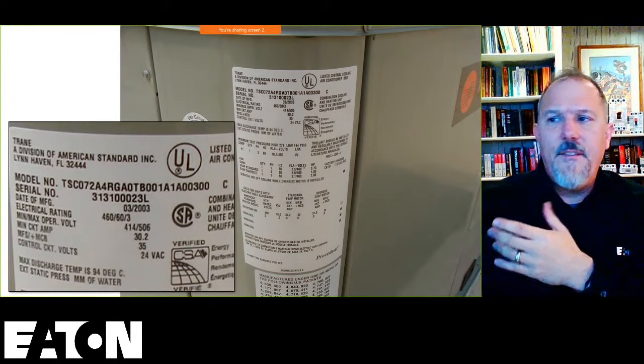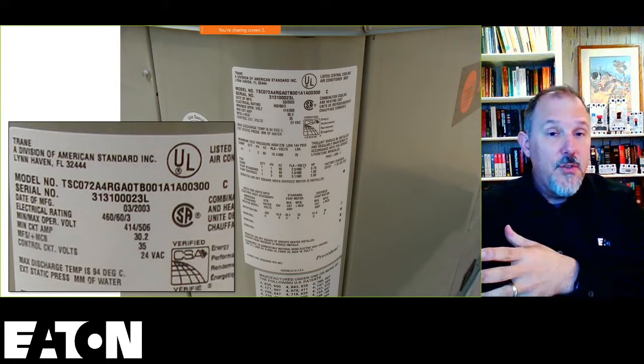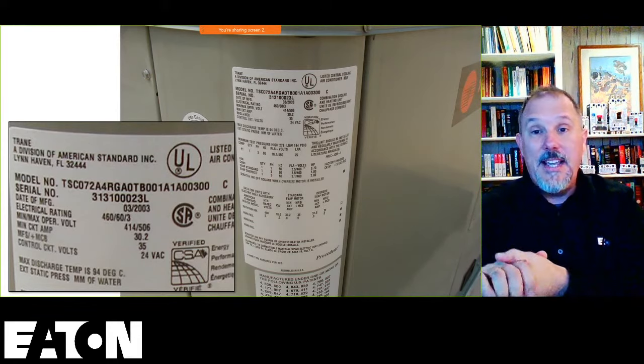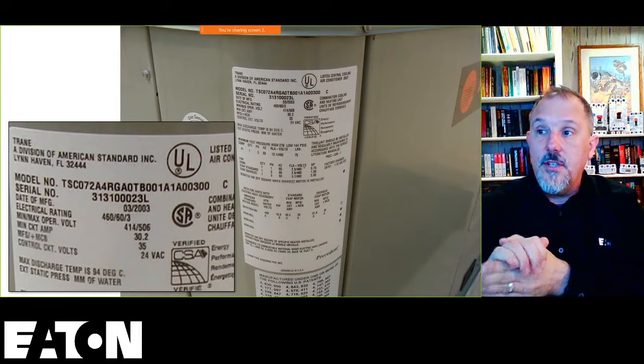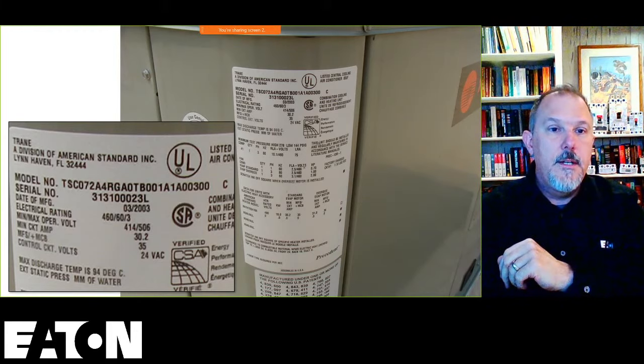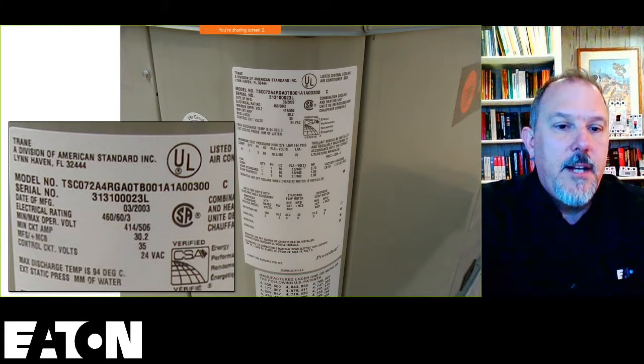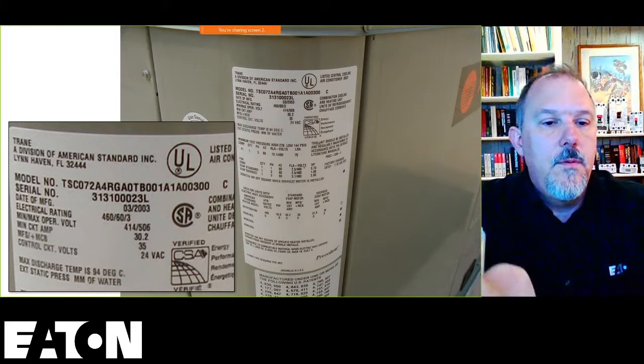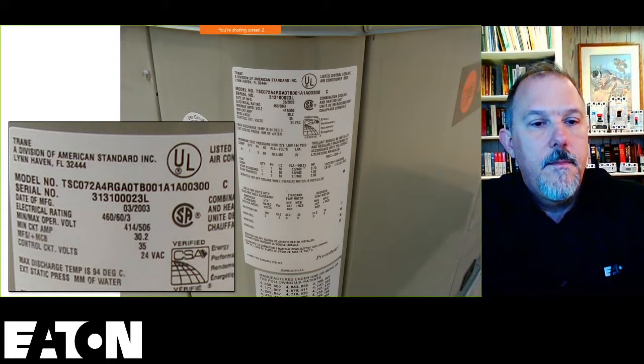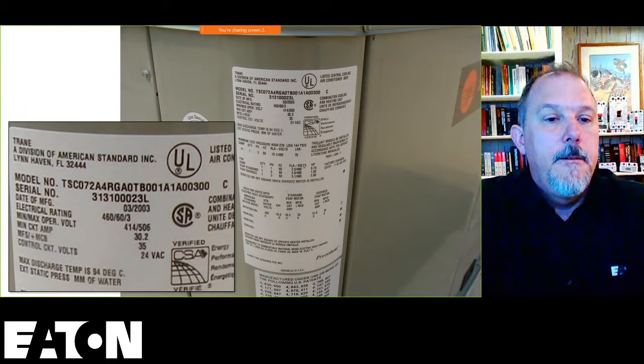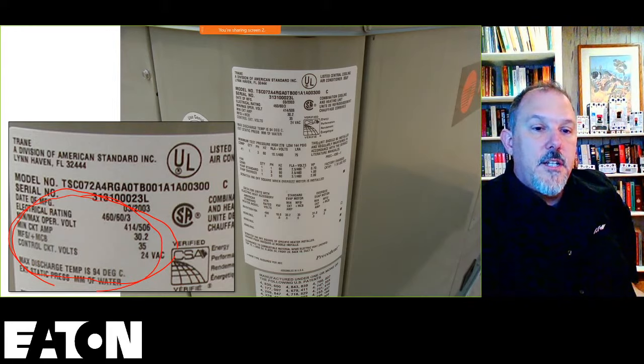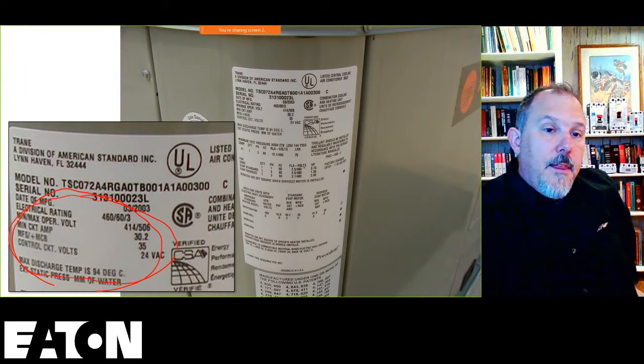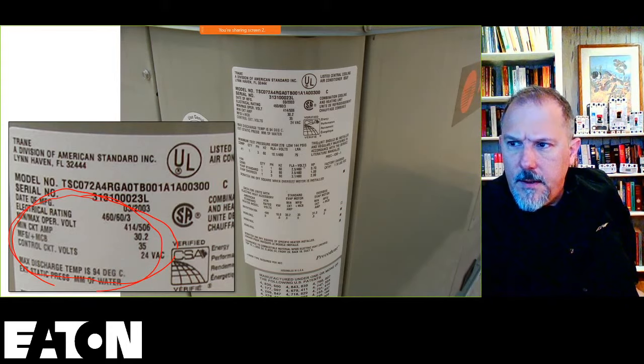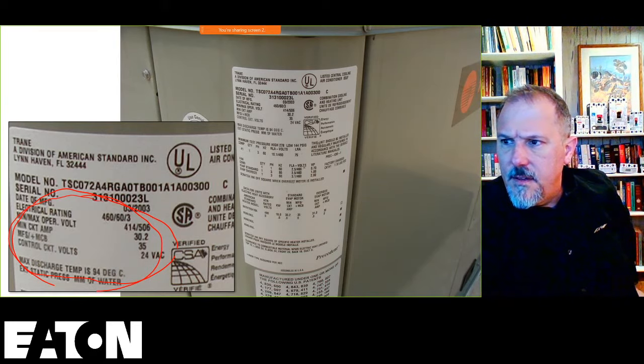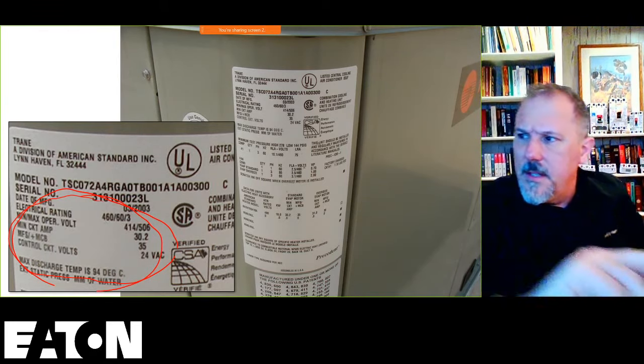And what you'll see is that you have the electrical rating 460. This is not one of those that were in my calculation. If I would have had this image, I would have made this one of my HVAC units. But you'll see the minimum circuit ampacity shown. Some critical information that we're using for our calculations: minimum circuit ampacity for this one is 30.2, and the maximum circuit breaker, I can't even read that. It says 35 MCB.